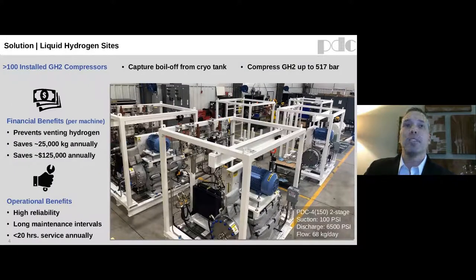The pressure builds up until it must be vented, losing valuable hydrogen in the process. Instead, PDC compressors can be used to draw hydrogen gas out of the tank. In this application, our PDC 4150 compresses from 100 PSI to 6,500 PSI ground storage pressure. The compressor saves 25,000 kilograms annually, worth about $125,000, and pays for itself in less than 2 years.